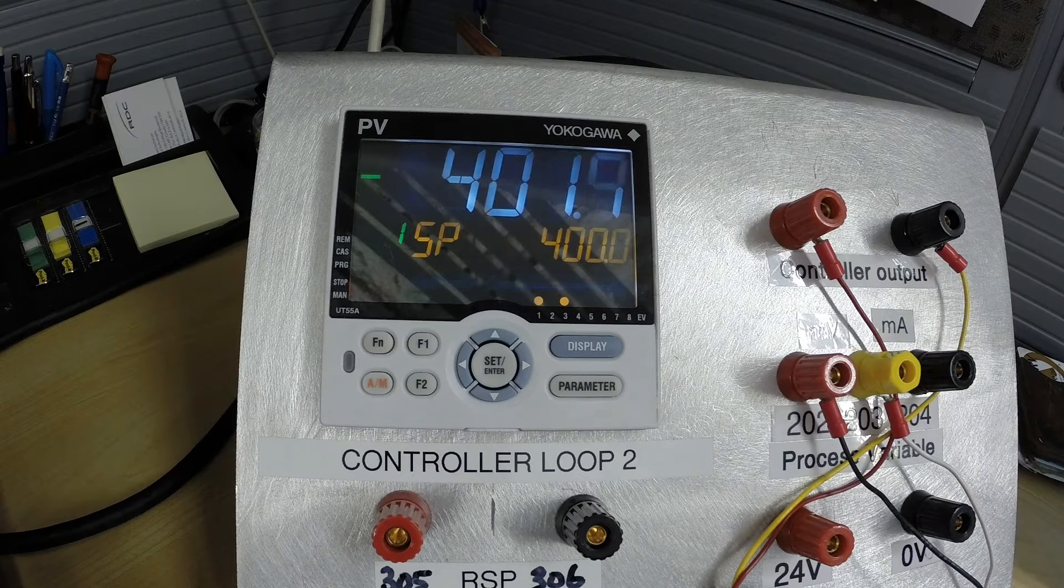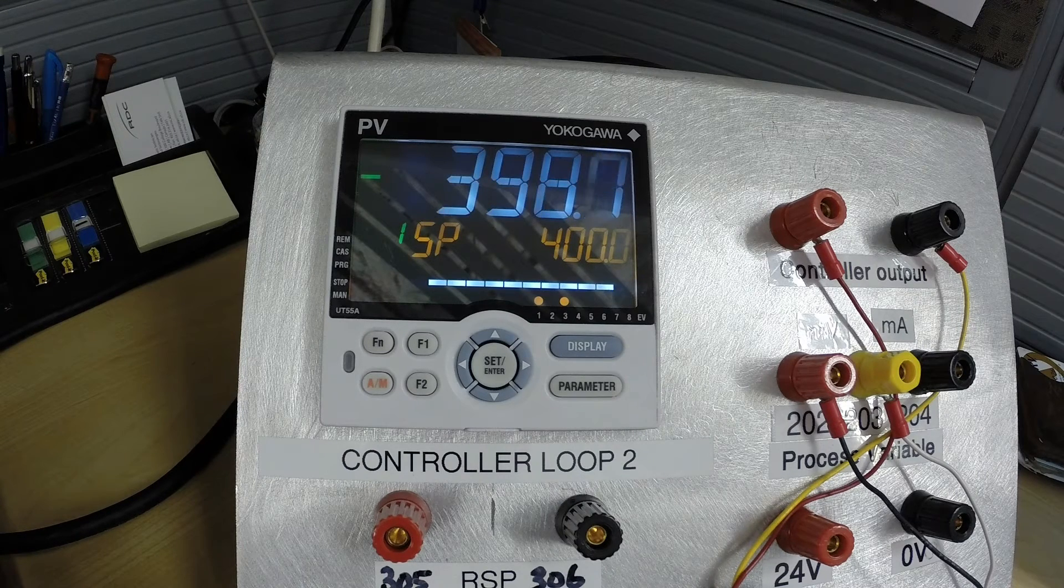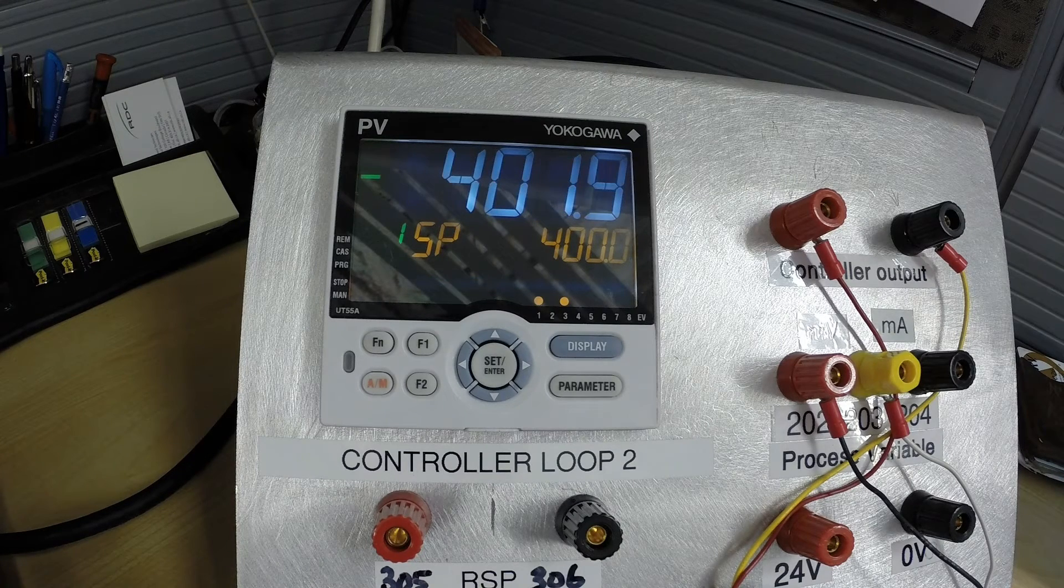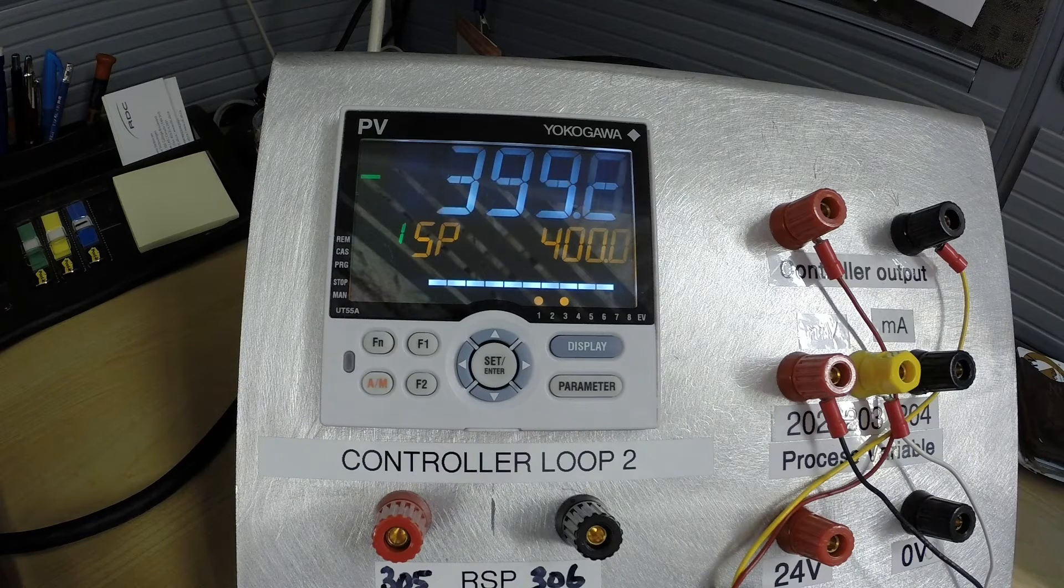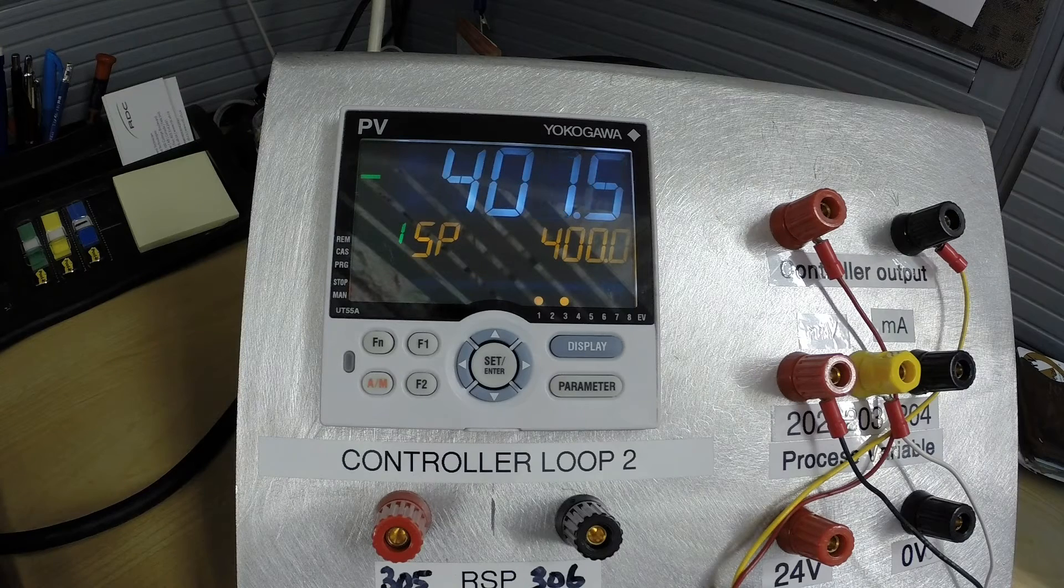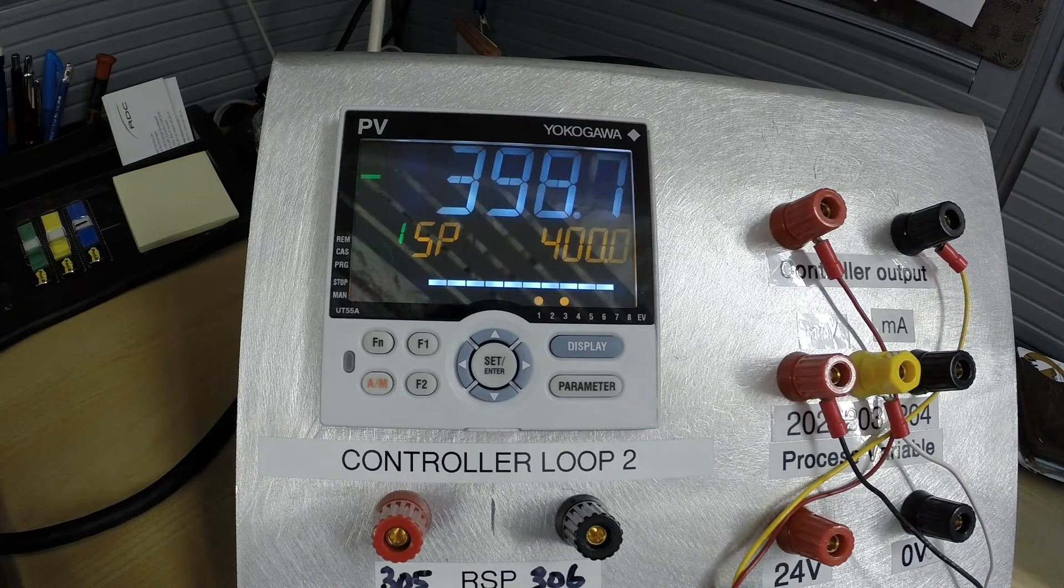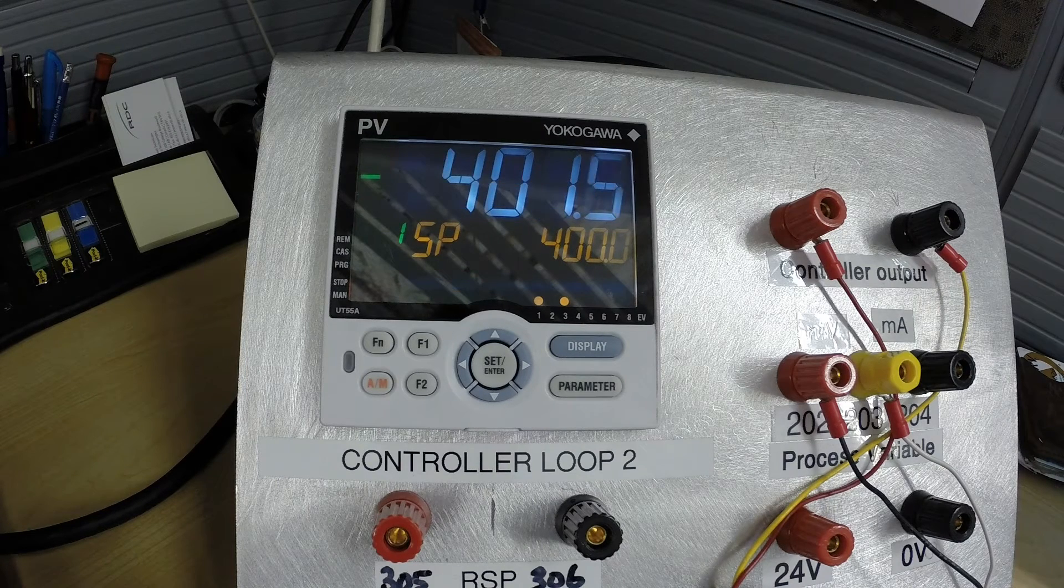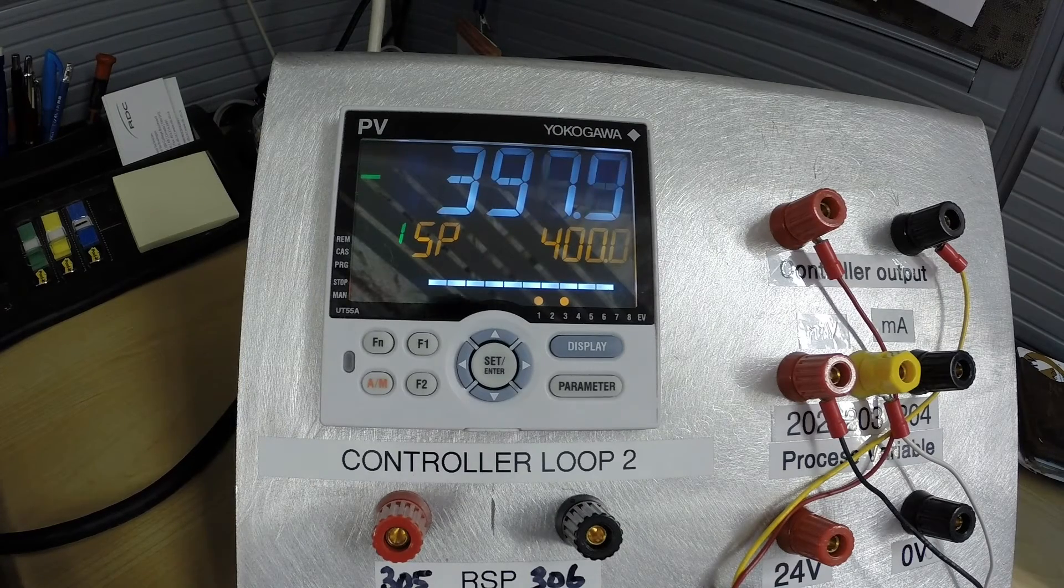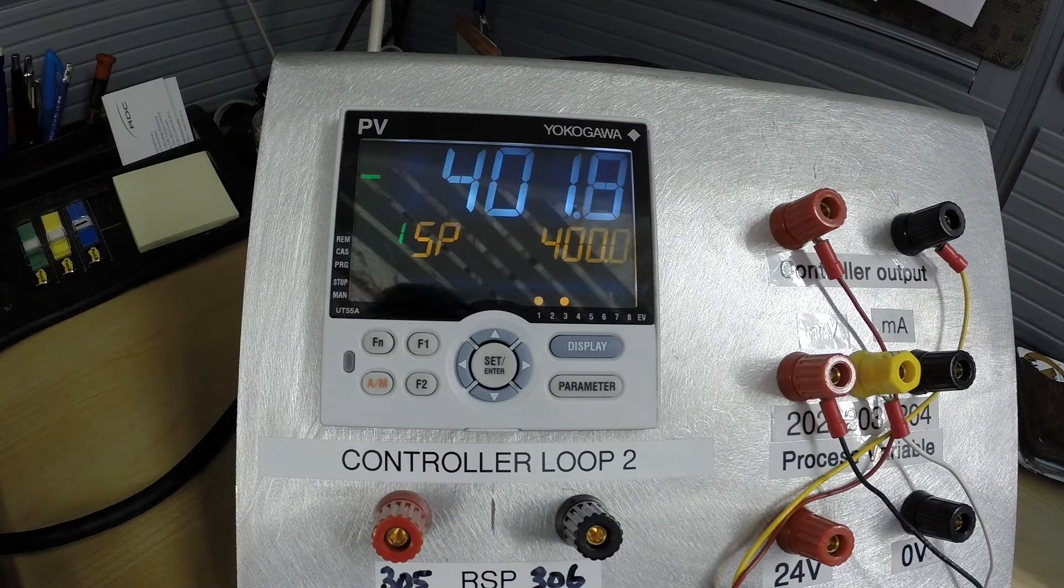From this point now we have our basic functions taken care of. We're going to go back into our parameter settings and set up a couple of alarm values which is one of the features of a single loop digital controller which is basically a single loop PLC. And we're going to go in there and set up a couple of alarm points so that we can demonstrate the display change when we reach an alarm level. So we can set up the controller to have the PV change color if we are in an alarm state.